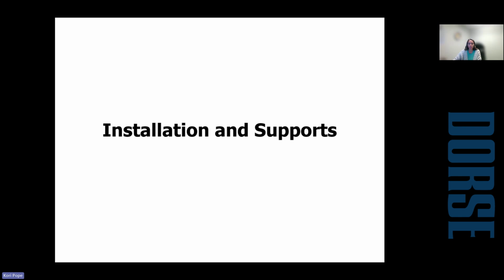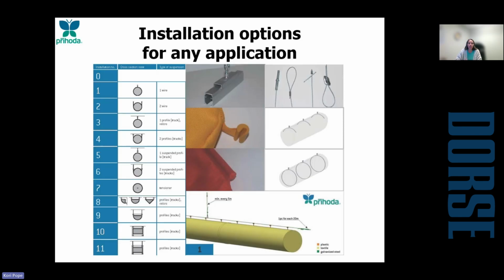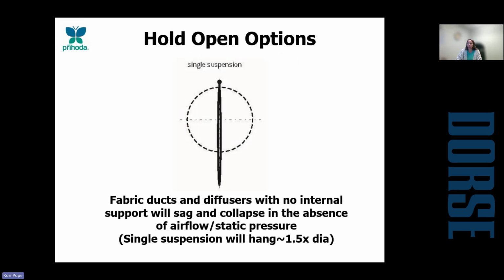So, installation and supports. We have a huge variety of mounting options, from just the simple single cable where the duct and the cable just clip together, to multiple track suspension systems to accommodate virtually any installation requirements. So one thing you have to be cautious of with fabric ducts is that our product is fabric. So if you don't have anything holding the duct open, it will collapse 1.5 times diameter when that unit turns off. And vice versa, when that air turns on, you're going to have all of the air coming down the duct at one time, and it will have a super loud inflation pop.